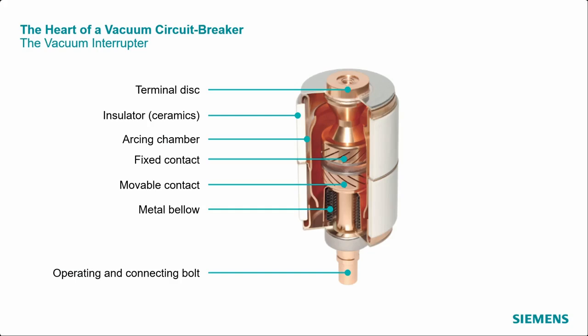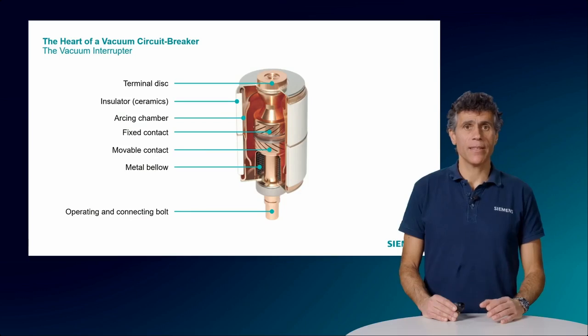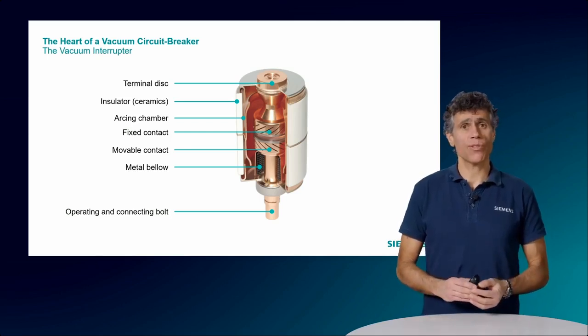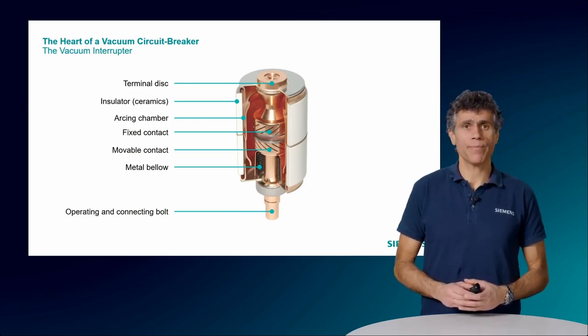The movable contact moves to make or break the electrical connection with the fixed contact. When the breaker operates, the movable contact pulls away from the fixed contact to interrupt the current and creates an arc in the arcing chamber that is quickly extinguished in a vacuum. Its design is conceived so that the discharge takes place in a smooth way, allowing the arc not to concentrate in one single point, and so not causing damage by melting or overheating the contacts nor components around them.